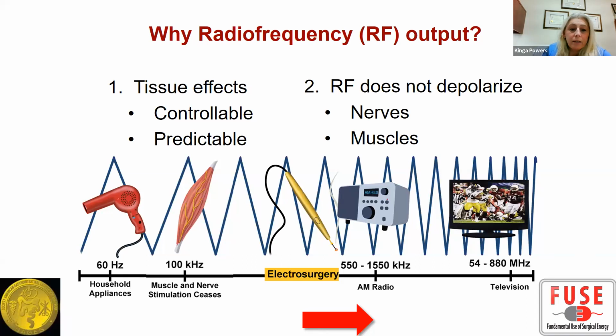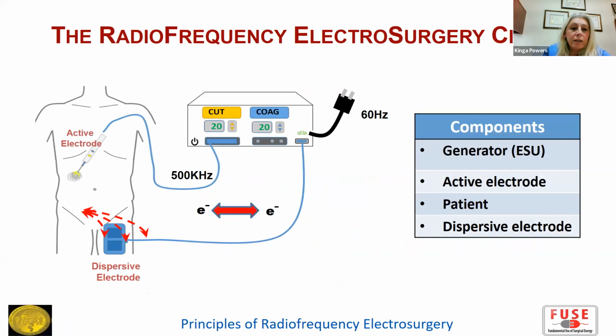So once we have the current converted, this is a picture of the electrosurgical unit, and it has a wire here that enters the active electrode. I don't know if you can see me pointing because I don't know if I have a pointer. Here we go. Here's the active electrode. And then the current travels through the patient to the dispersive electrode, which is wider, and it gets dispersed and travels back to the electrosurgical unit. So the elements of the circuit are the ESU, the active electrode, the patient, the dispersive electrode, and then the current travels back to the ESU. And there's no grounding. There's no connection to the ground anywhere. The current travels back to the ESU.